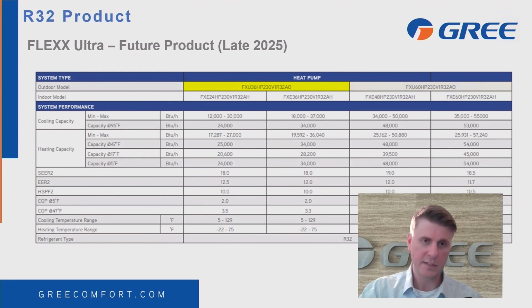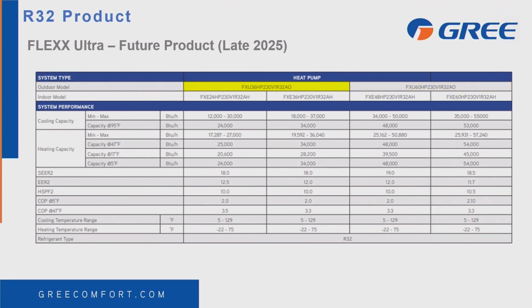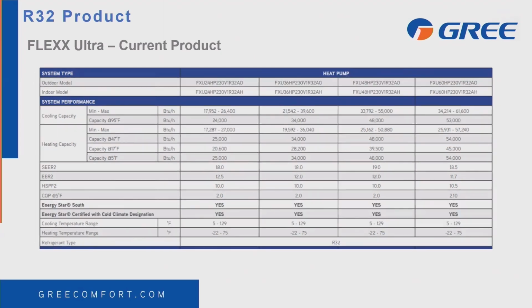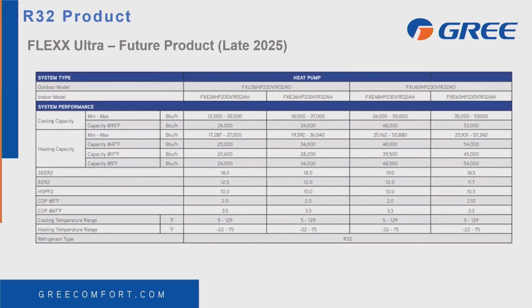And with the 36K, you're going to switch the dip switch on the outdoor unit to get you a 24K capacity or a 36K capacity. Same thing on the 5-ton. You just change a dip switch to determine whether you're getting a 48K or a 60K. And then depending on your application, you'll buy the indoor model that corresponds with that. On the indoor models, you can notice that there was a model number change. So on the first slide, the indoor model says FXU. On the second slide, you see the models to the indoor unit change to an FXE.